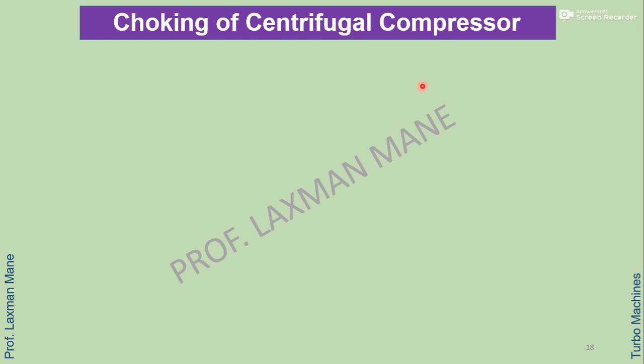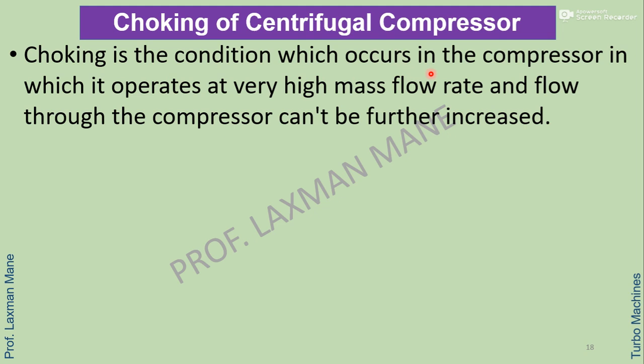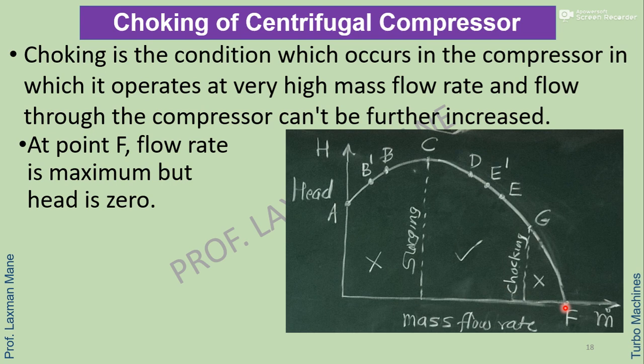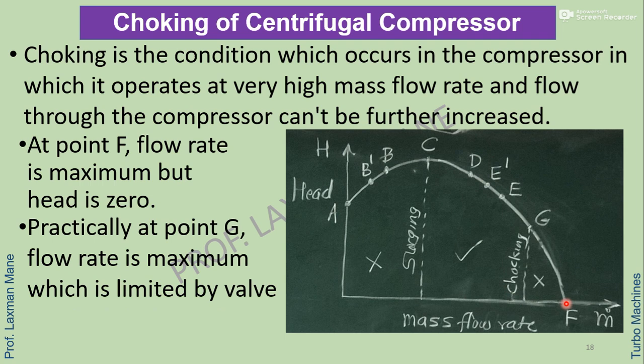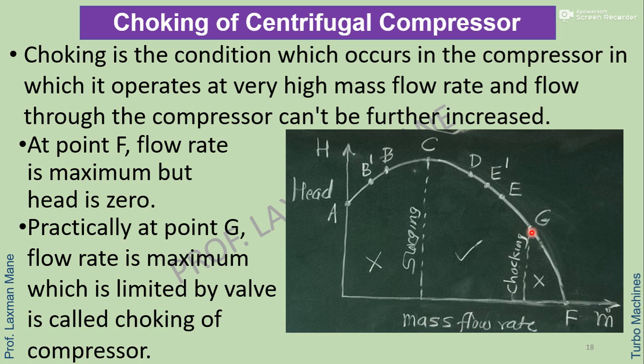Choking of centrifugal compressor: choking is the condition in which the compressor operates at very high mass flow rate and flow through the compressor cannot be further increased. From the diagram, at point F flow rate is maximum but head is zero. Practically, at point G flow rate is maximum but is limited by the throat — this is called choking of the compressor. Beyond this point, mass flow rate cannot be further increased.